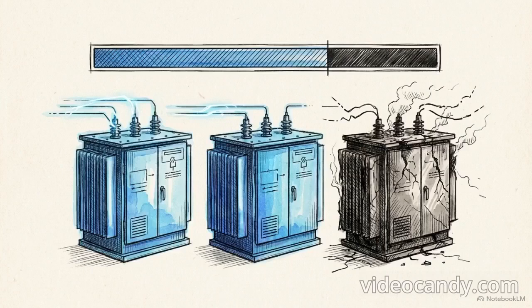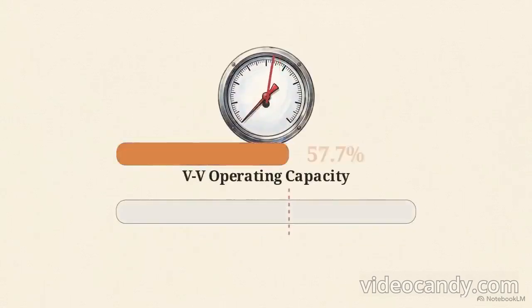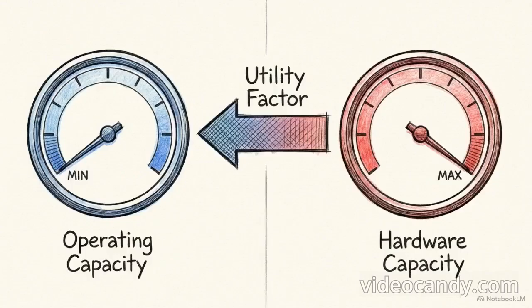If one transformer in a closed delta-delta bank burns out and fails, the symmetry is broken. To maintain 3-phase service, engineers can run the remaining 2 units in an open delta, or VV architecture. You might assume that keeping 2 out of 3 transformers means your capacity drops to roughly 66%. The math dictates otherwise.